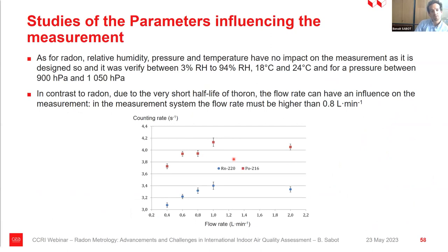In our system, it was developed so that humidity, temperature, and pressure do not have any effect. The only remaining effect is the flux of air inside the system. Below some flow rate, the thoron is not homogeneous inside the measurement device. So we have to use it at a flow rate higher than 0.8 liters per minute.